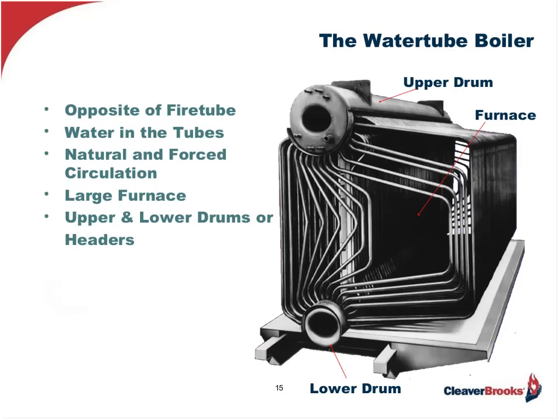The water tube boiler is just the opposite from the fire tube — the water is in the tubes and the fire and hot gases surround them. Many water tube boilers on the market today have been designed to naturally circulate the water-steam combination through the tubes, utilizing properly sized tubes connected to drums or headers, providing the pressure density differentials required for natural circulation. However, there are other water tube designs which require forced circulation, incorporating their own pump, and in a steam application these are referred to as steam generators.